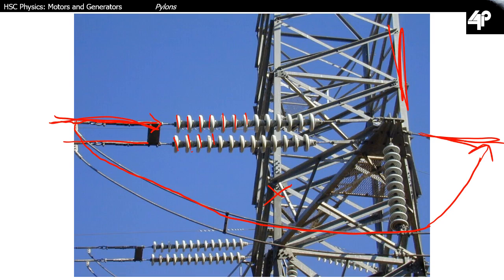These insulators are stacked together in a big line, and the more you've got in the stack, the more insulation it provides. So the higher the voltage being carried through the lines, the more insulators you need in this chain. If it was a little bit shorter, the electricity would simply arc across to the pylon and connect that way.